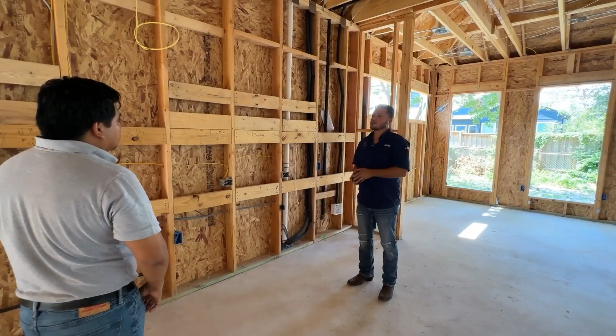So how does the vent hood talk to that? There's going to be another pipe coming down from this one. The reason we left it like that is because you're going to have the ceiling first, then the cabinet, then we come back and do another pipe coming down. This pipe here is going to have a transformer and a pressure switch as well. Whenever you turn on the vent hood, that pressure switch activates, and that's what opens the makeup air.